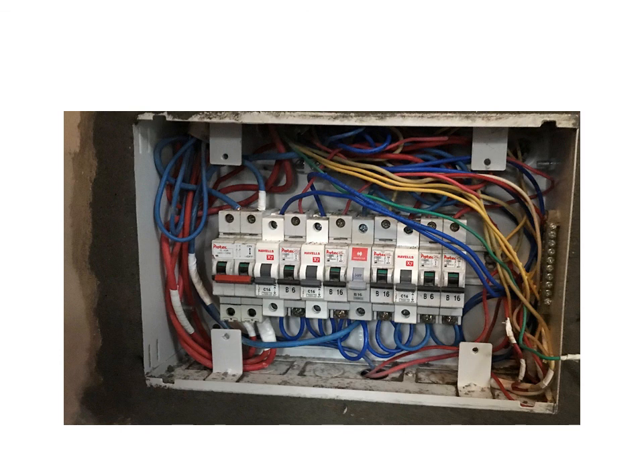So on the left hand side you can see the double pole MCB, that is the main switch. Both phase and neutral go through this MCB, and then neutral goes to the neutral link. So here ELCB is also not connected. If we want to connect ELCB, after the main switch, that is the double pole MCB, ELCB will be connected, through which phase and neutral will go, and then the output is taken from the ELCB, then phase to the bus bar, and neutral from ELCB to the neutral link.